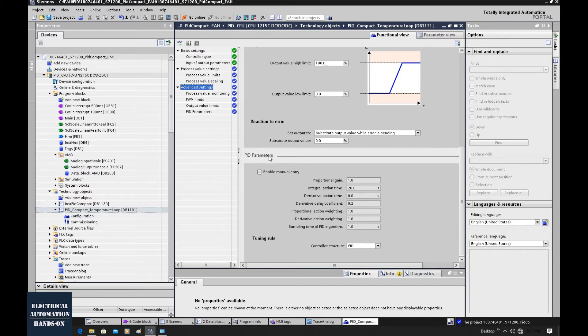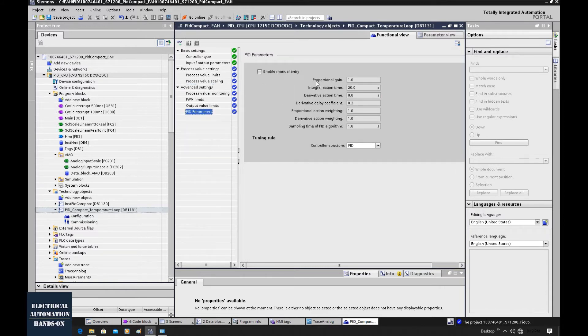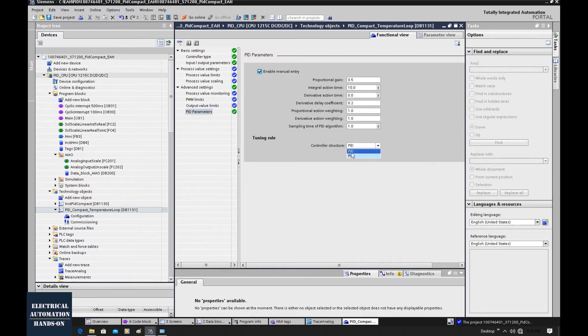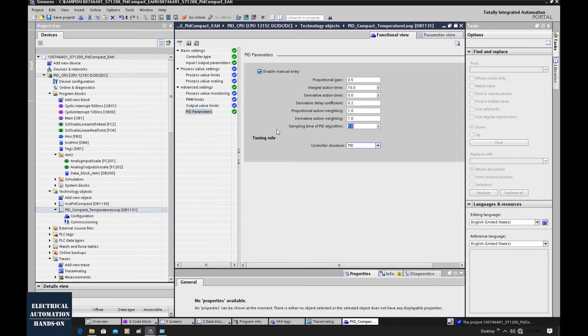After those preliminary settings, let's shift to the main section: gain, integral, derivative, and coefficients. We can click this button to switch to the PID parameters individually. To change the PID parameters, we click this button which allows us to manually set the initial parameters. For example, we can set the gain to 0.5 and the integral action time to 10. Here you can also select PI control or PID control. An important parameter is the sampling time of the PID algorithm — usually we set this equal to the cyclic interrupt that calls the PID compact function block. In our case, the PID loop runs under a 100-millisecond cyclic interrupt, so we set 0.1.